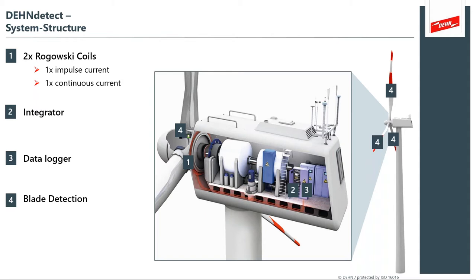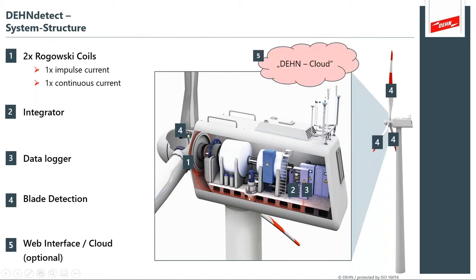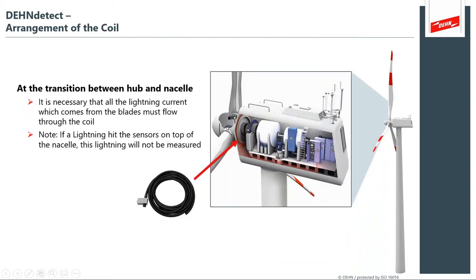It's actually quite a simple system, but it's important that it's installed directly on the blade nacelle at the root, right where it's entering the hub, and then directly around the inside of the nacelle around the rotor in a wide enough circle to capture all available flux. The arrangement of the coil actually has to be installed around the rotor shaft in a wide arc. You don't want to snug it against the rotor because some currents flow through the slip rings and other parts of the entry into the nacelle. It's important that the Rogowski coil creates a big enough loop around the inside of the nacelle to capture lightning flux.